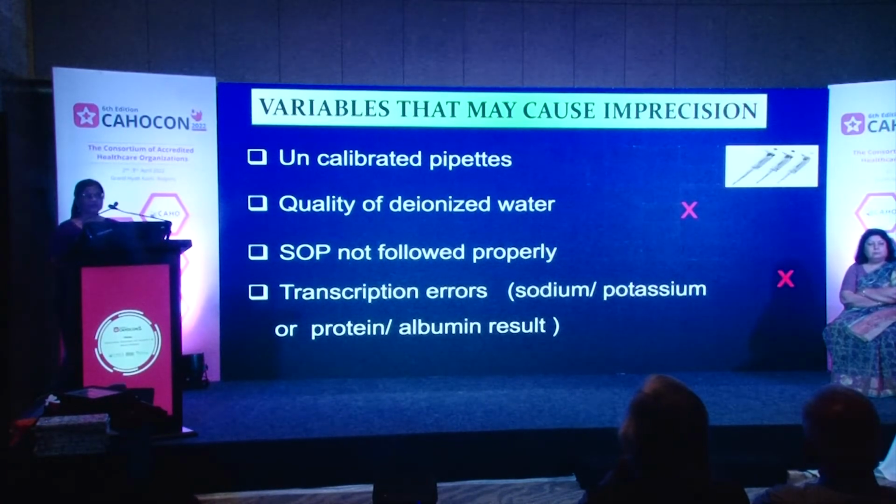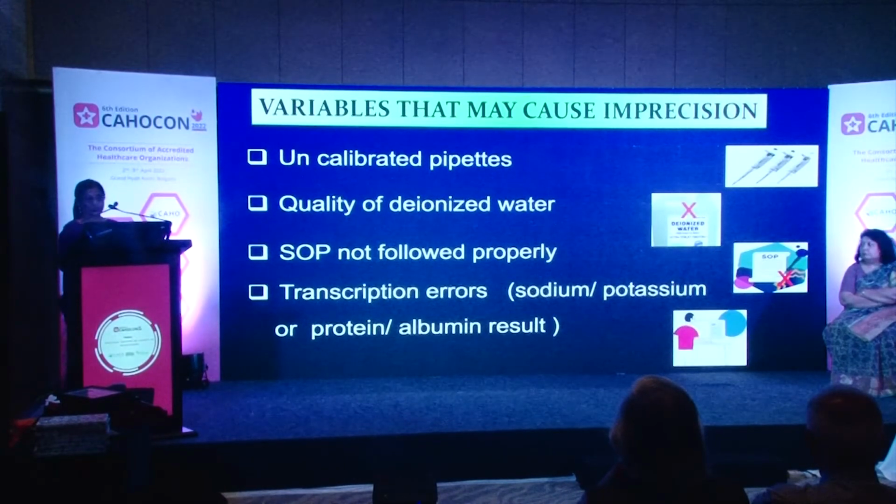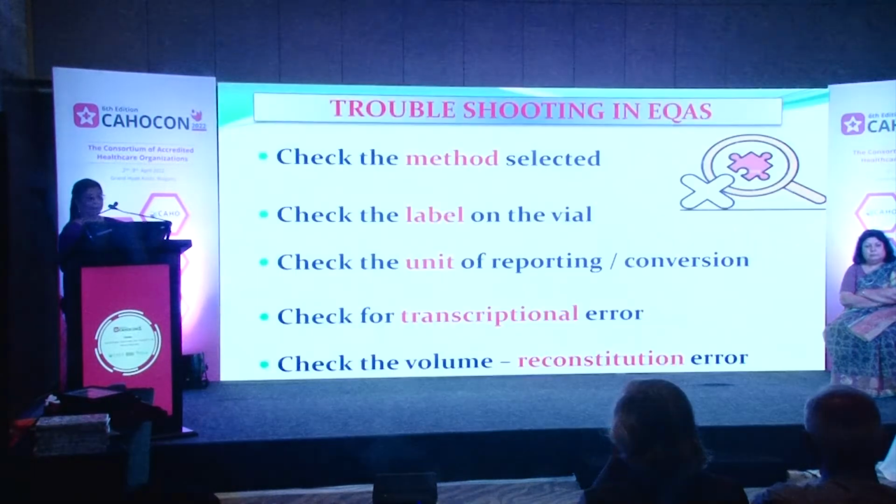Uncalibrated pipettes. This is what we have got as feedback from some of the participating laboratories. Wrong quality of deionized water, SOP not followed properly, transcription errors. Many laboratories enter sodium and potassium, and they mix up between them. Protein and albumin also get mixed up.